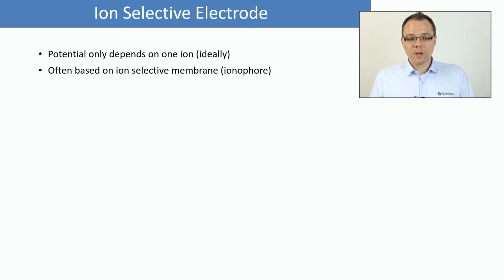you let through. And I already said, yes, they're based on a membrane. So you just want to have the potential depend on one ion. And one way of doing it is taking your electrode and putting a barrier between your electrode and your measurement solution that will only let one ion through. So usually that's in this barrier, which is usually a membrane, so a thin layer. There's an ionophore in there that will transport ions through this layer, and you want it just to be specific ions in an ideal case for your electrode.